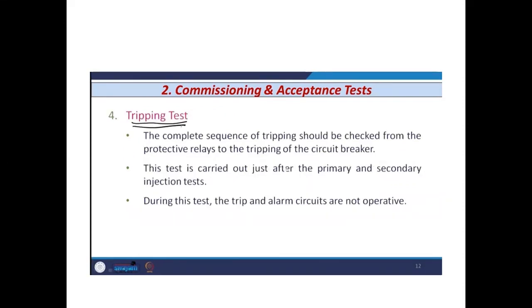The fourth type of commissioning and acceptance test is the tripping test. The complete sequence of tripping should be checked from the protective relays to the tripping of the circuit breaker, from the very beginning till the end. This test is carried out just after the primary and secondary injection tests. So as you can see, we are discussing all these tests in a sequence.